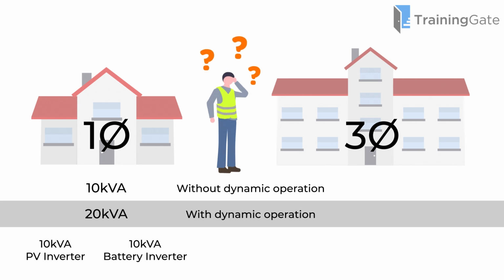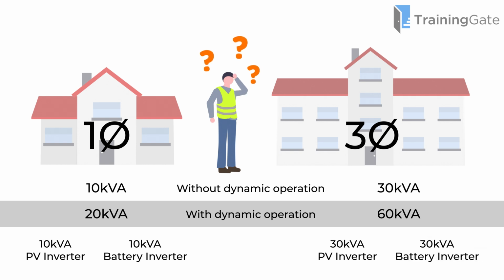Similarly, three-phase sites can support up to 10 kVA per phase without dynamic operation and up to 20 kVA per phase with dynamic operation, again split between PV and ESS inverters. Dynamic operation can allow for greater flexibility and higher total inverter capacities on both single and three-phase sites.